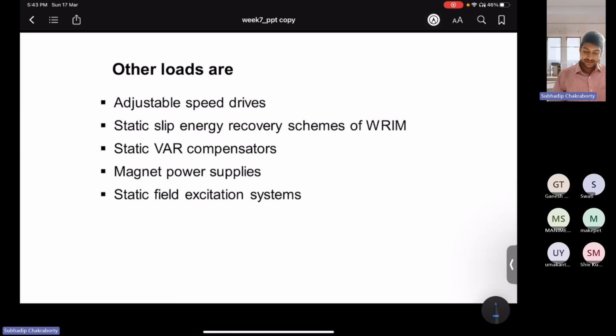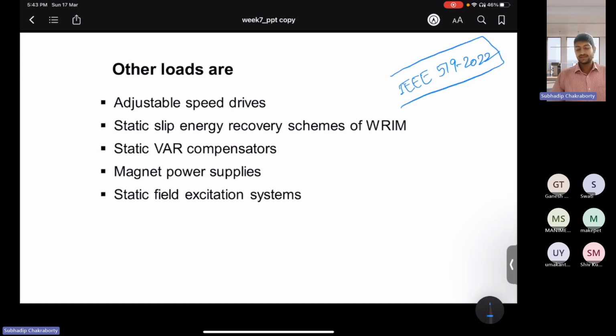Okay, power quality standards as per the IEEE 519-2022 standard, right? You just look it up on the net. You search it with IEEE 519-2022. You will get a PDF document, and just go through it. It will discuss the current quality standards as per industry standards, how to actually model your system, and what the requirements are from a grid operator's perspective, that you should not throw more harmonically distorted currents, and if you have more harmonically distorted load currents, you need to compensate them and then connect your system with that of the grid, because you cannot push that high harmonically distorted current into your AC mains, right? There are some standards, so 5% is allowed at the grid side. You cannot push beyond that.